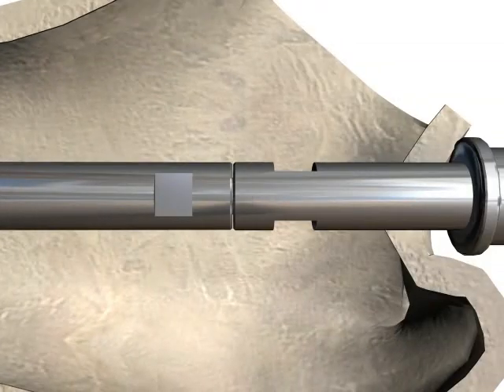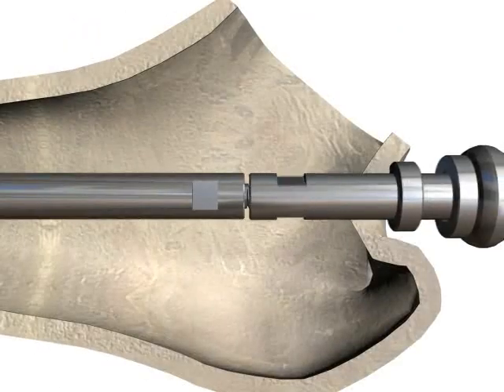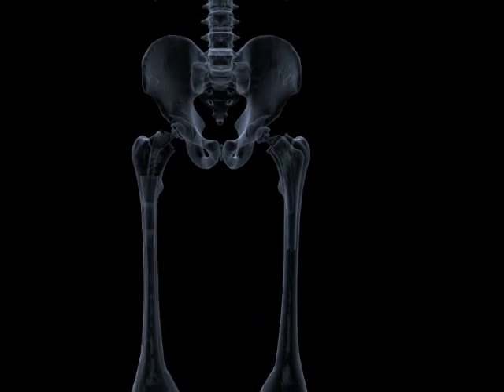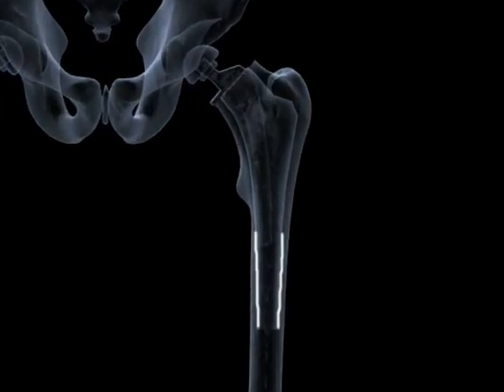The handpiece can then be detached and the slap hammer connected. Do not put excessive force on the slap hammer when in use. X-rays will give a good indication for use of the extraction probe. Ensure there is good bone stock, loosening or delamination of the cement, an even tapered canal, and the cement lies above any isthmus. Incorrect use or positioning of the probe can easily lead to fracture or a concertina effect in the canal.